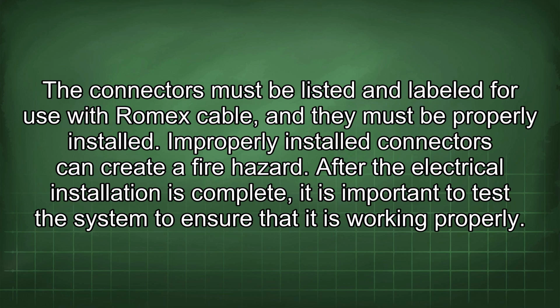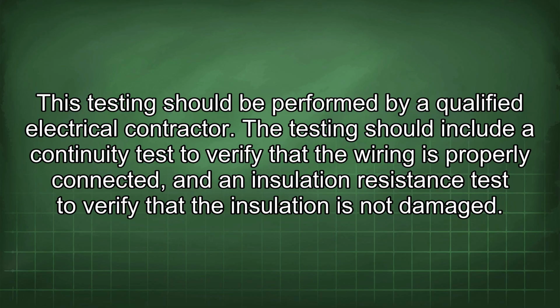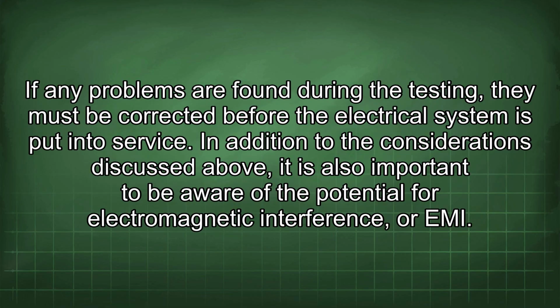After the electrical installation is complete, it is important to test the system to ensure that it is working properly. This testing should be performed by a qualified electrical contractor. The testing should include a continuity test to verify that the wiring is properly connected and an insulation resistance test to verify that the insulation is not damaged. If any problems are found during the testing, they must be corrected before the electrical system is put into service.